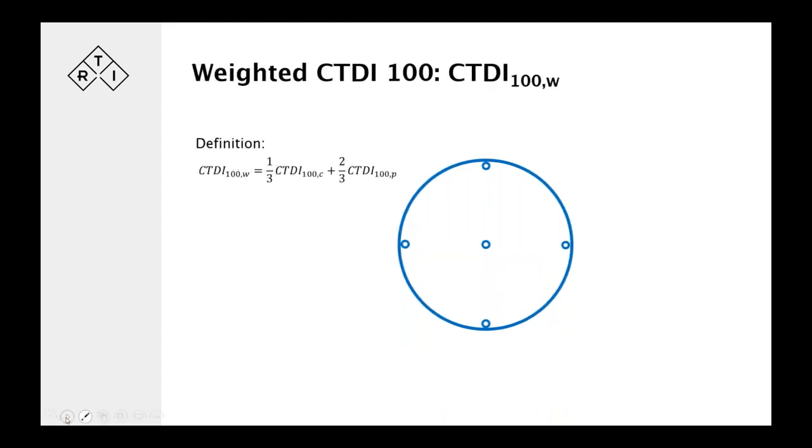All right. So CTDI is one thing, CTDI 100 is another thing. Weighted CTDI was then also introduced to take into account the effect on the skin. The phantom simulates a body, so the center measurement is the organ dose or penetrated dose. But it's also interesting to see what happens at the skin level or just below it.